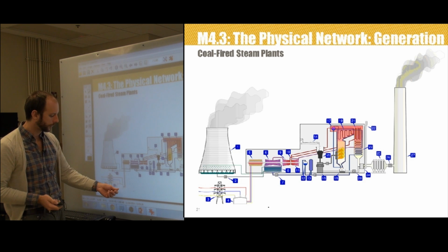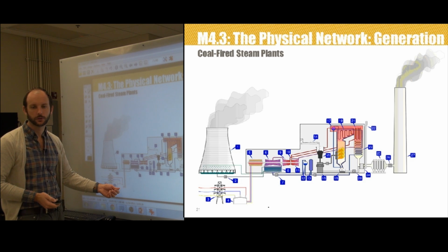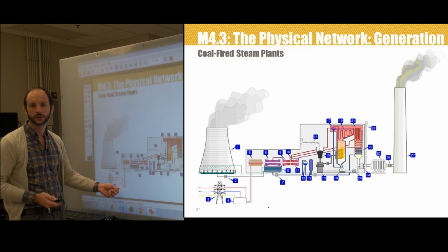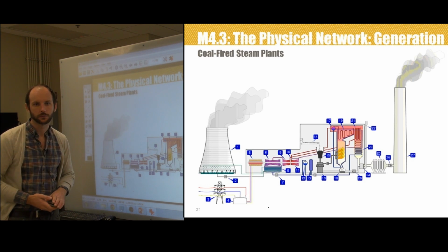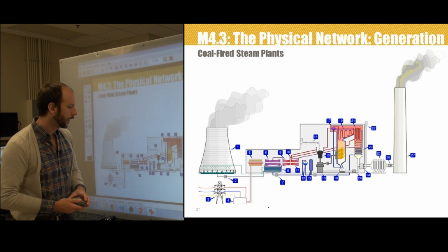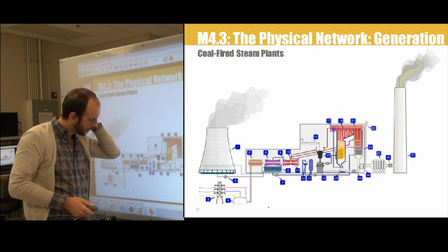It's stepped up at the generation site by a transformer to a voltage more suitable for transmission, 72 kilovolts or higher, up to 500 kilovolts or so, and then it's just sent out on this number 3, the three-phase transmission system.